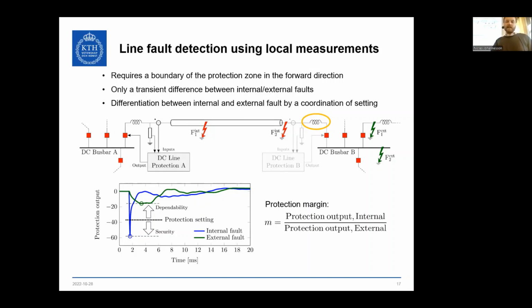In this case, it's only using local measurements, meaning the protection on the left side needs to differentiate between this remote internal fault F2 and the two external ones.